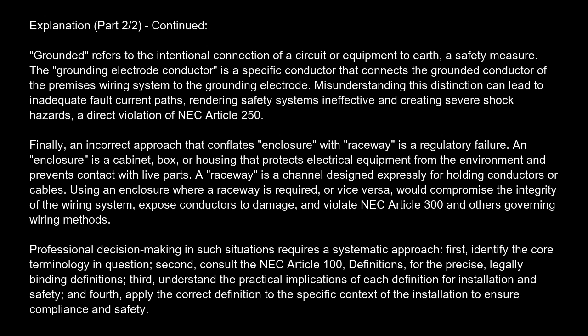Finally, an incorrect approach that conflates enclosure with raceway is a regulatory failure. An enclosure is a cabinet, box, or housing that protects electrical equipment from the environment and prevents contact with live parts. A raceway is a channel designed expressly for holding conductors or cables. Using an enclosure where a raceway is required, or vice versa, would compromise the integrity of the wiring system, expose conductors to damage, and violate NEC Article 300 and others governing wiring methods.